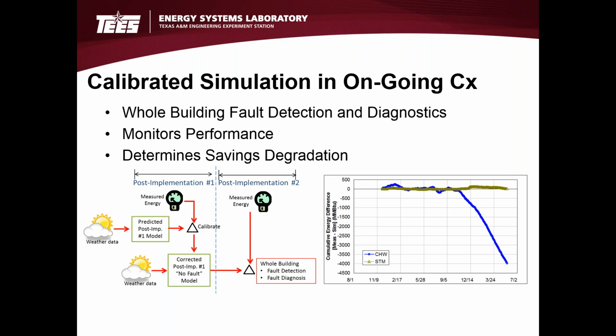When we went to the building with this information and they checked, they happened to have a district chilled water supplier, and lo and behold, on the very day where we saw that performance break away, they had come in and recalibrated their chilled water meter.